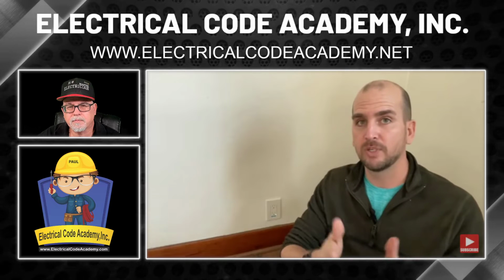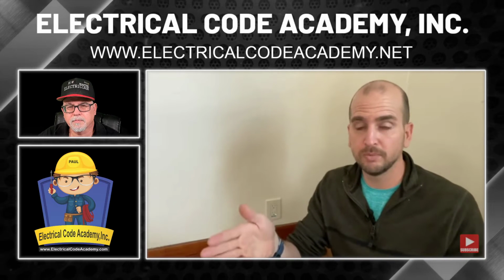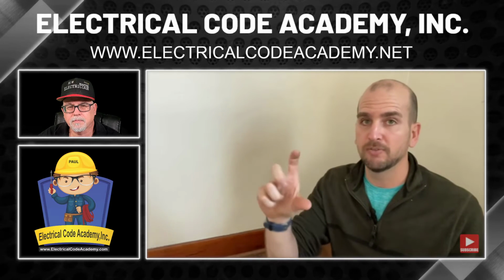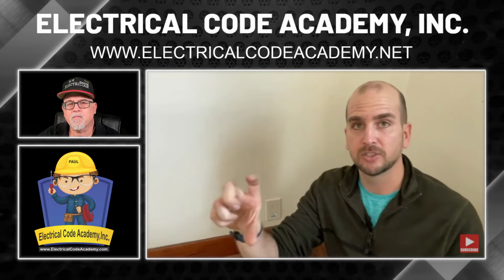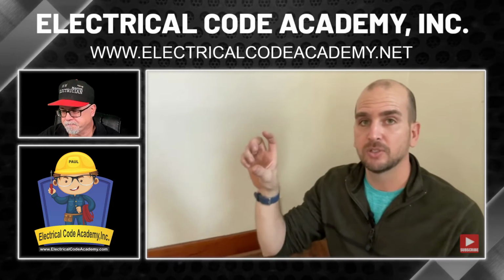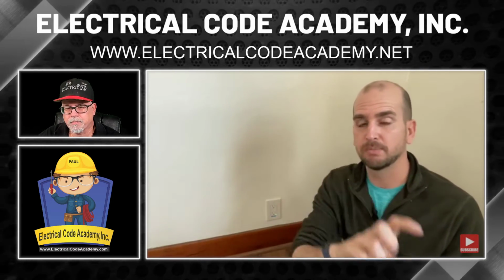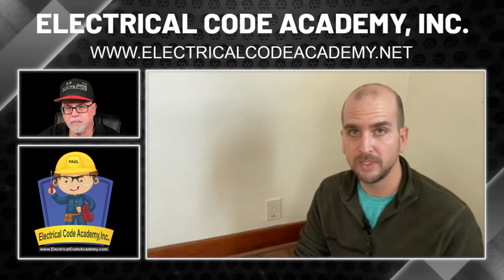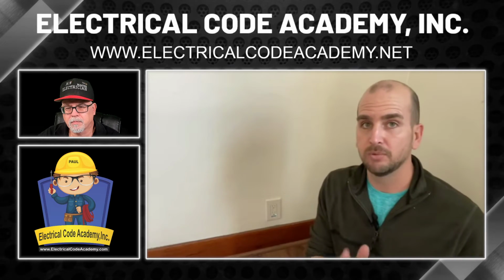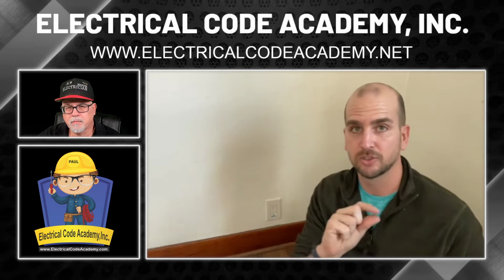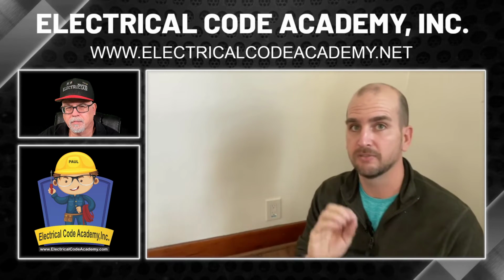Now again, getting a little more complex, but I just wanted to let you know that if you have three or four receptacles in a room, there is a possibility if you install a GFCI at the starting receptacle that you could just install standard receptacles at the other two or three and they would still be covered. Now you still will need to label that there's no equipment ground on that faceplate to follow NEC.